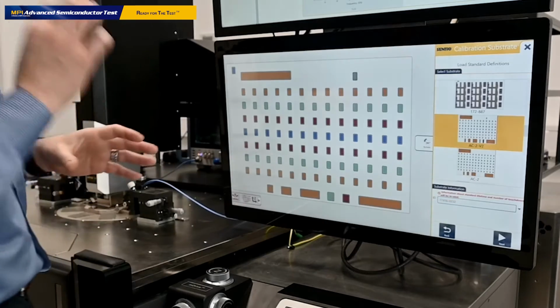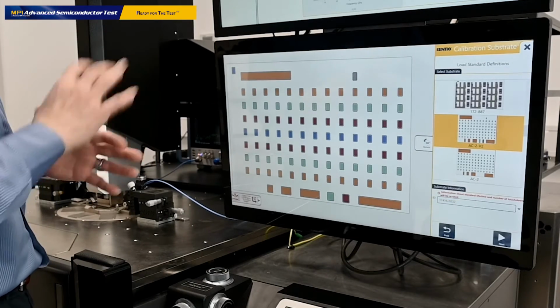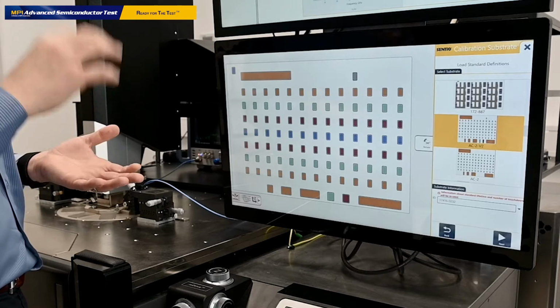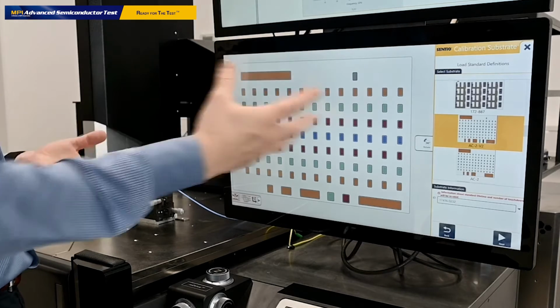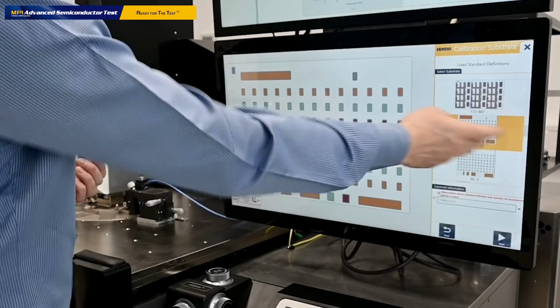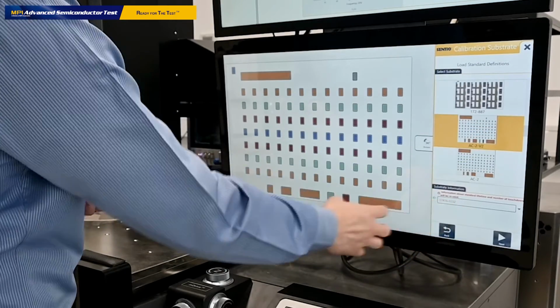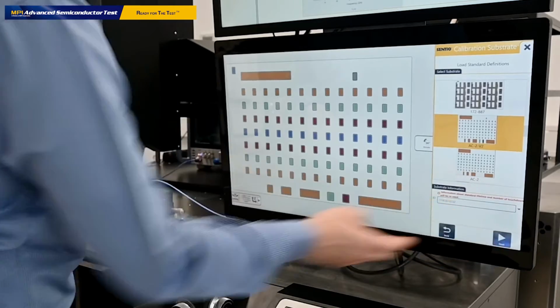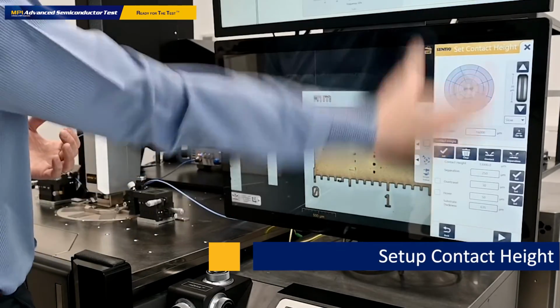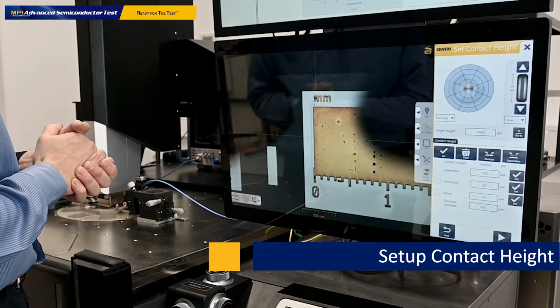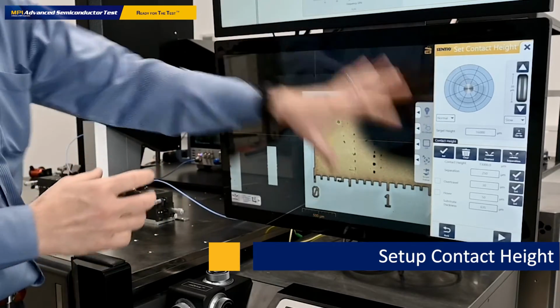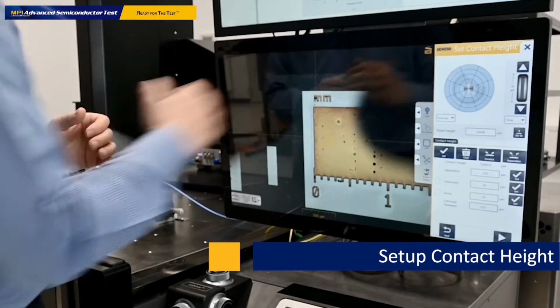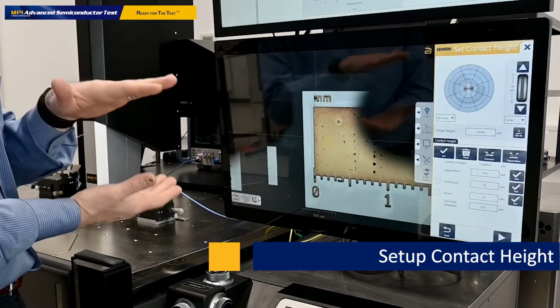This is the one which I currently have here on the system. Define its ID, and definition of ID is important because Sentio also tracks the number of touchdowns of a particular calibration substrate, and I will show you how it works a little bit later. So after we selected the calibration substrate type, we know the ID is correct, we move to the next step. The graphical user interface is automatically switched to the big window, which gives us the whole overview of the current location of the calibration substrate. And our first step is to set up contact height.